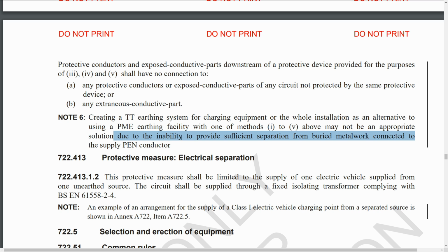ground there, because if you, say, had a cable coming to a property, it's going to have main bonding to the gas and water supplies, and if the gas pipe, say, was metallic, which a fair number of them still are, and that was going under the driveway, if you put in an earth electrode and it's, say, half a metre away from that gas pipe buried under the ground, when a fault occurs, the PEN conductor voltage will rise above the normal ground, and because you've got that metal conductor under the ground, and it's only, say, half a metre from your actual electrode, some of that voltage is going to show up on that electrode you've put in, and of course that's going to completely ruin the whole point of having it in the first place, because then all the stuff connected to that is again going to have that dangerous voltage on it.